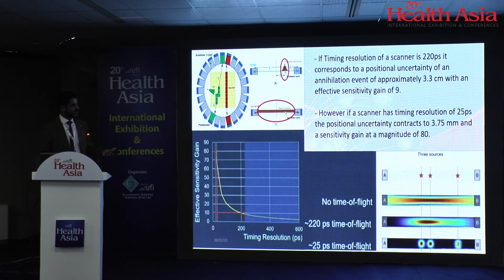Here is an example: a non-time-of-flight PET-CT has three sources, and the scanner must find the origin of the annihilation event throughout the entire line of response. A PET-CT scanner with a time of flight of 220 picoseconds contracts that uncertainty; at 25 picoseconds you are precise. Right now in the industry, the minimum time of flight achieved by any manufacturer is 196 picoseconds.